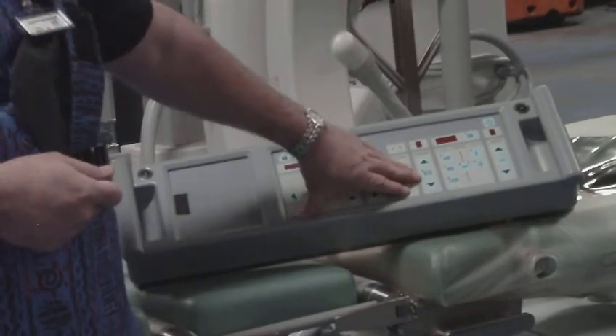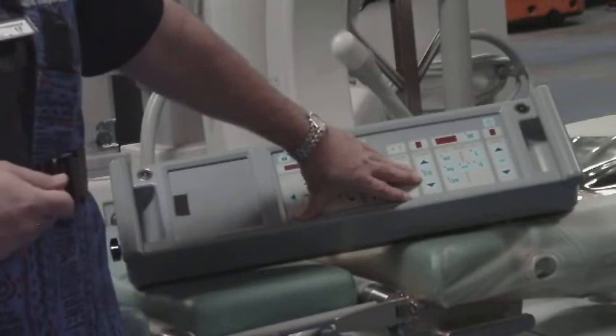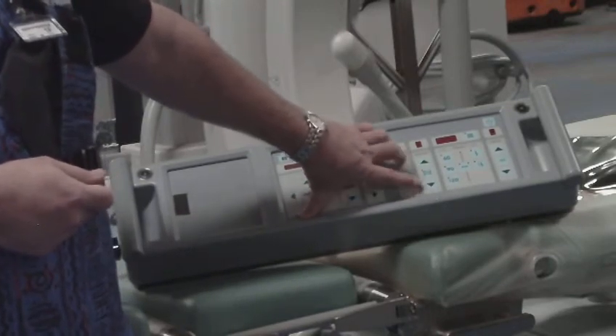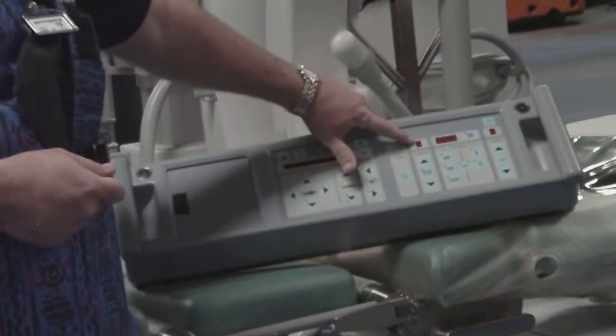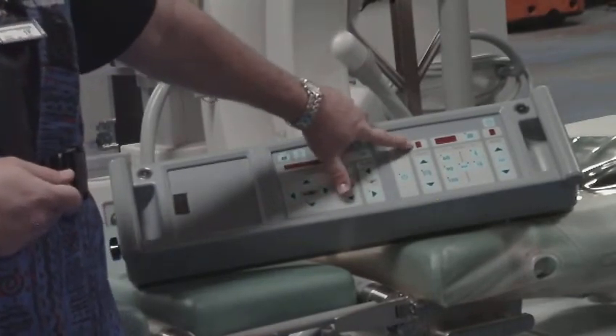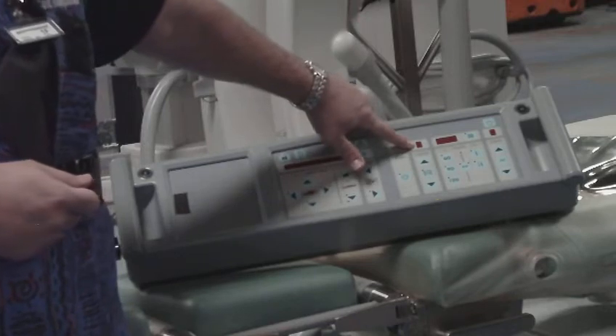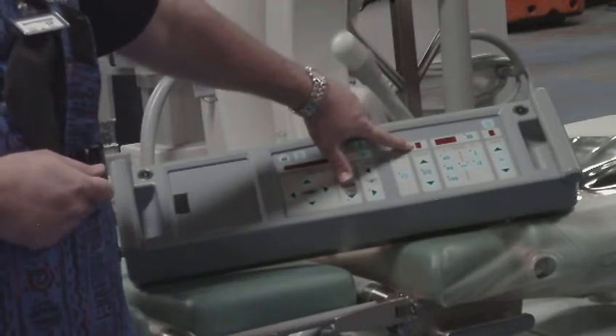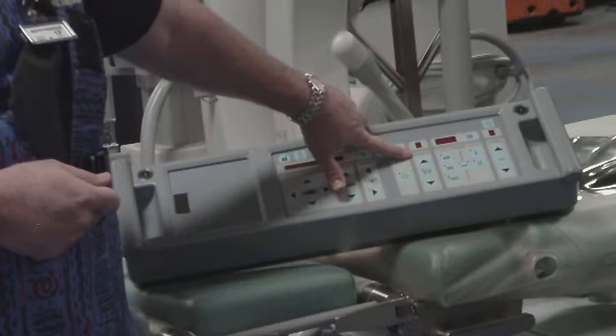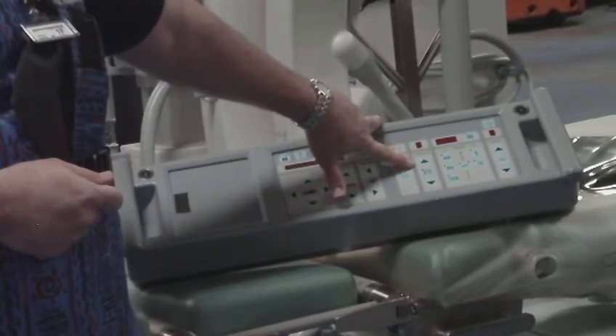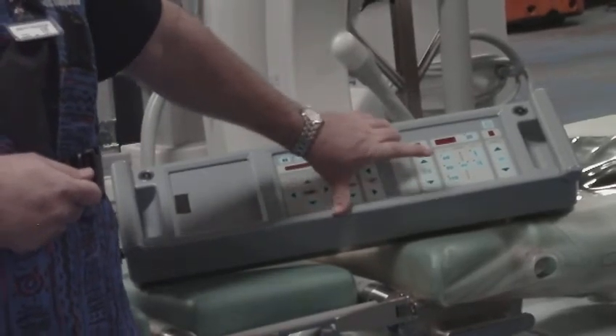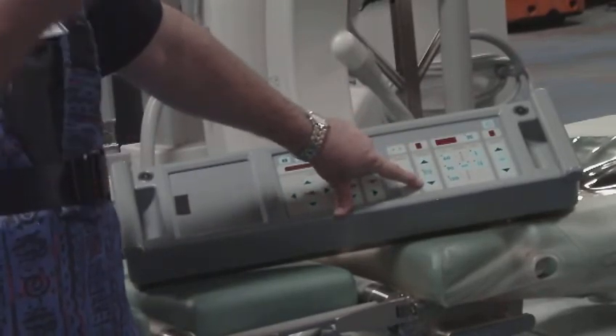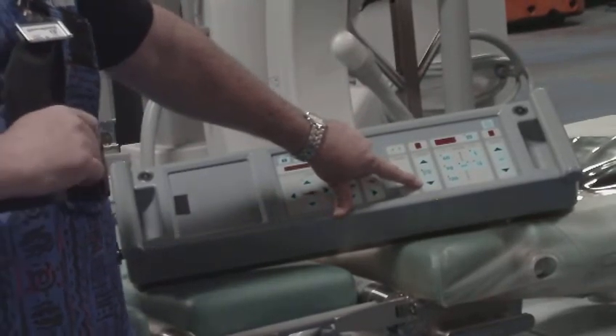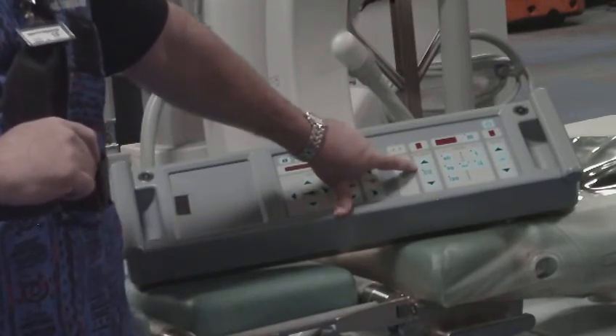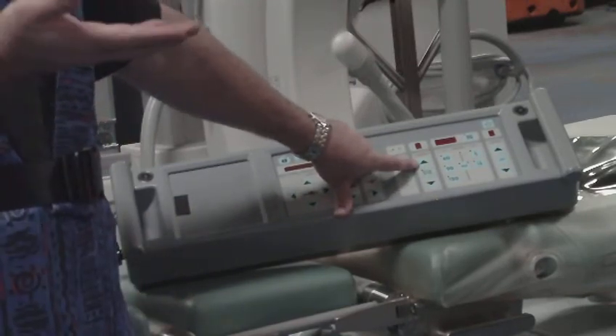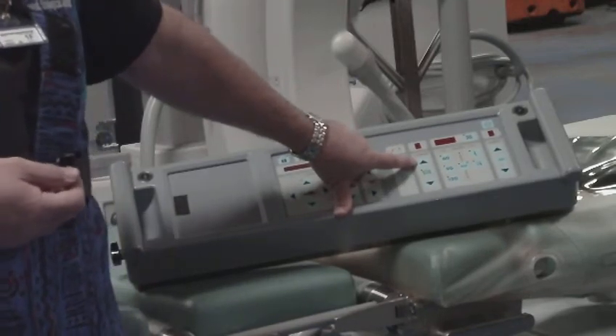This button here is your airbag cushion pressure. More pressure, less pressure. The number will come up here and tell you at what pressure level you're at. If you have a larger patient, you're going to want to decrease your cushion pressure to be able to get them closer into the Z-axis. Sometimes with a smaller patient you need to increase it to push them away from that treatment to get them closer to the Z-axis.